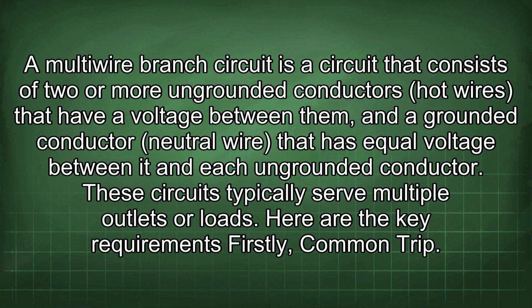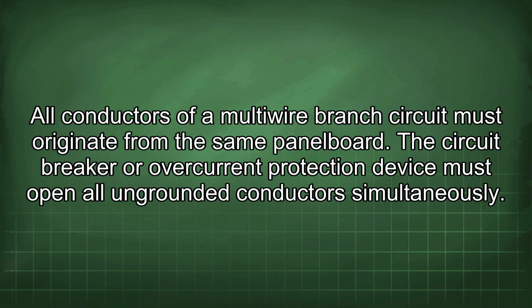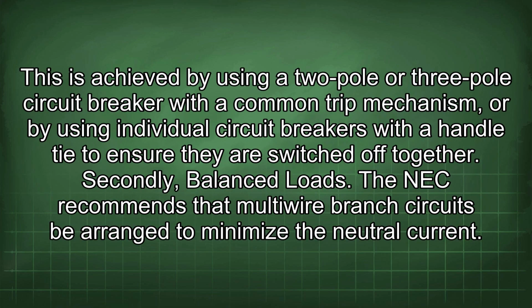Firstly, common trip. All conductors of a multiwire branch circuit must originate from the same panel board. The circuit breaker or overcurrent protection device must open all ungrounded conductors simultaneously. This is achieved by using a 2-pole or 3-pole circuit breaker with a common trip mechanism, or by using individual circuit breakers with a handle tie to ensure they are switched off together.